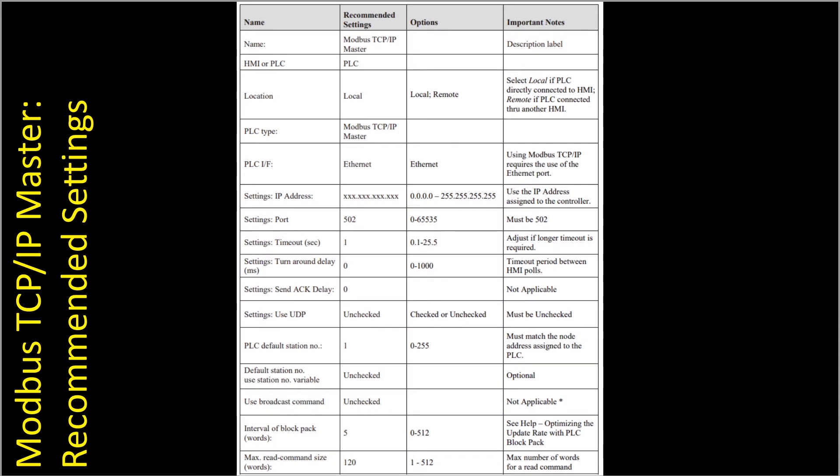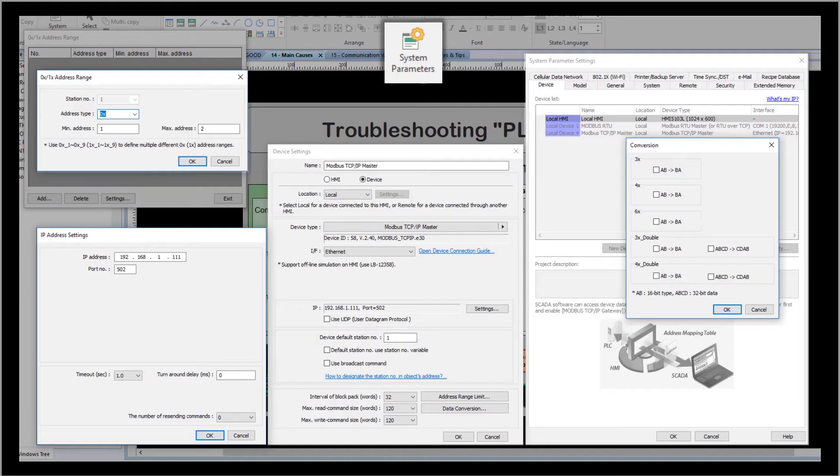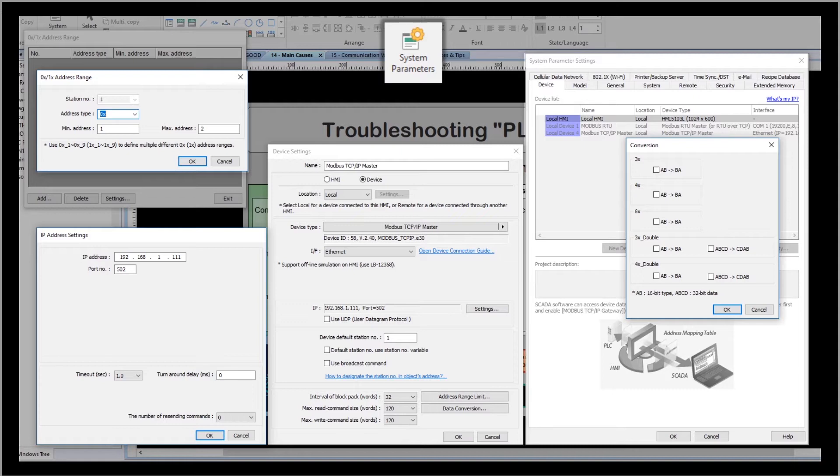Now having covered the cabling let's look at an example. Here we have a controller information sheet for a Modbus TCP IP master device showing here. If we wanted to add this device driver to our EB Pro project we would do that under the system parameter settings window click on add a new device and then apply all the settings accordingly and depending on the controller you may need to review a wide variety of parameters. These will be listed in the controller information sheet.